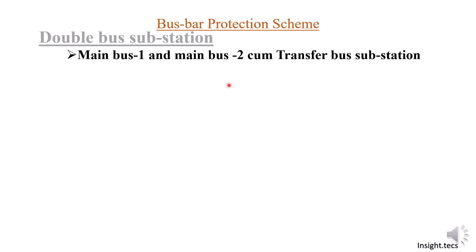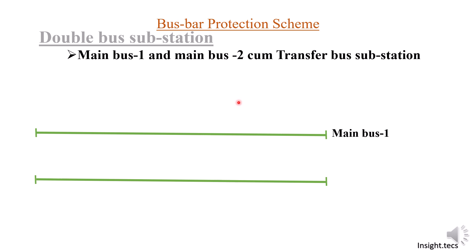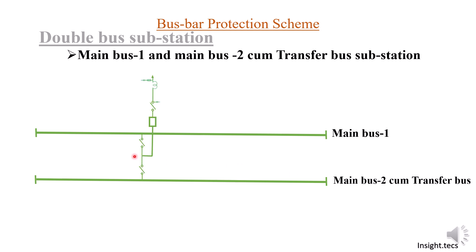You have a double bus substation, but you can get the benefits of a three bus substation. The first bus is main bus one and the second bus is main bus cum transfer bus. The second bus plays the role of both main bus two and the transfer bus.